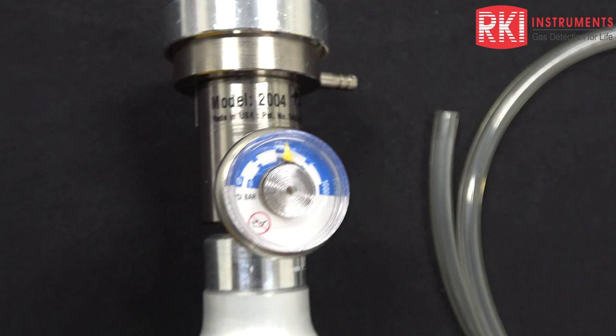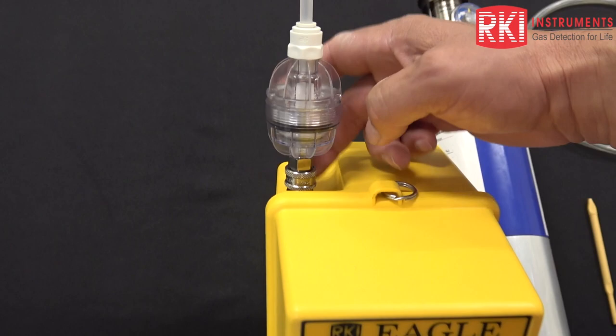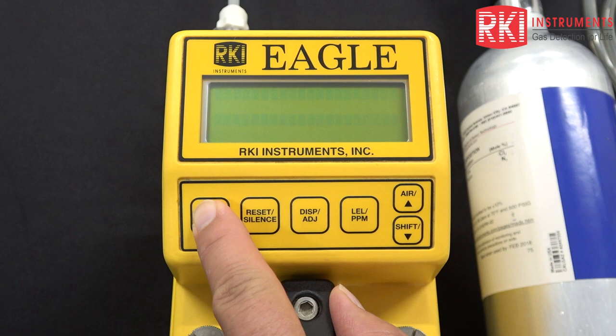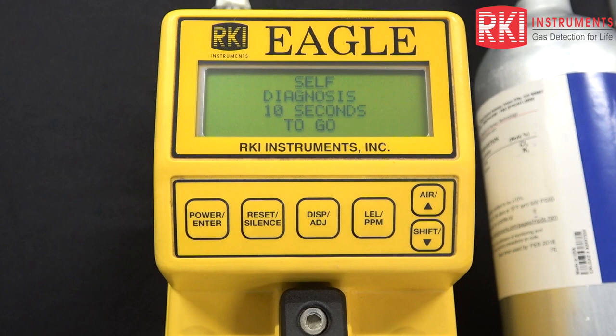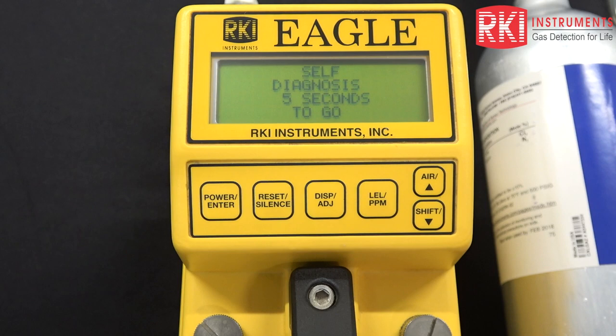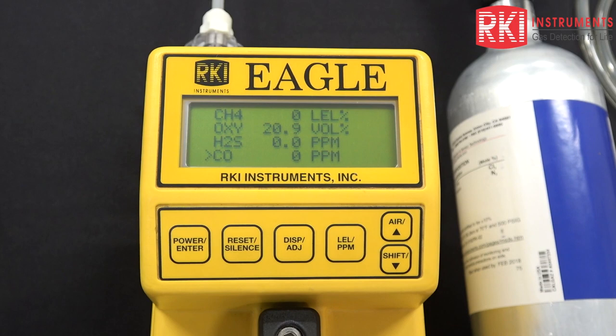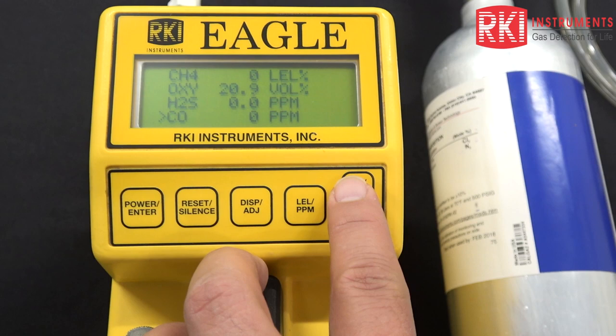I've got the probe attached via the quick-connect fitting already, so it's nice and snug. Now we're just going to turn the unit on and do an air adjustment before we do any calibrations. It's displaying the minimum battery and current battery voltage, going through a diagnostics countdown. After it goes through this countdown, it's going to display the active gases online. Everything is okay and we are going into normal operation. At this point, I want to press and hold the air button.